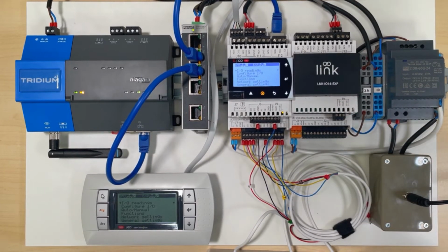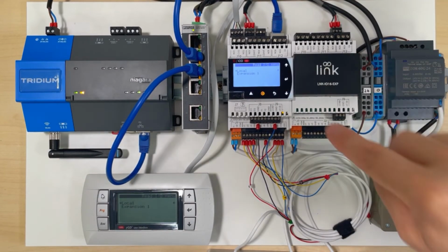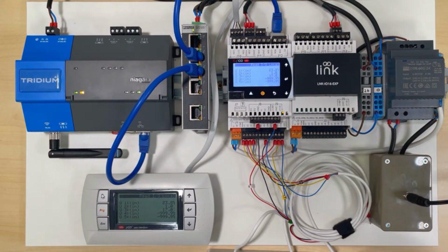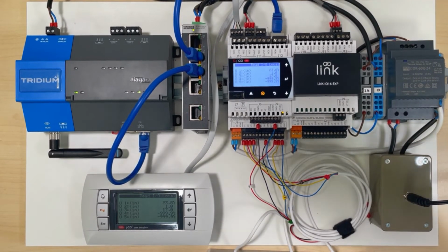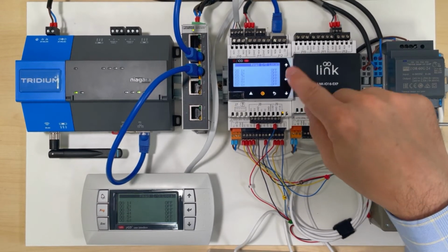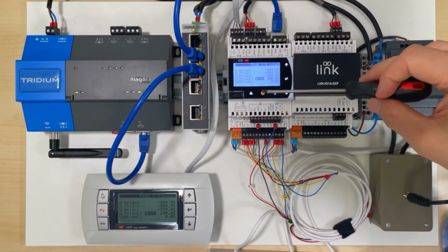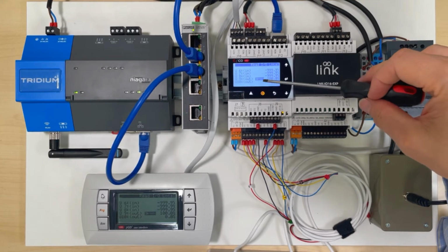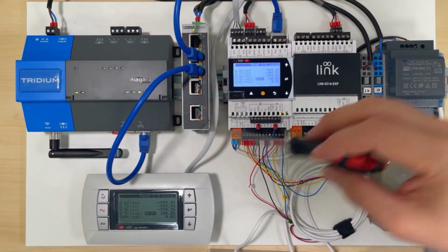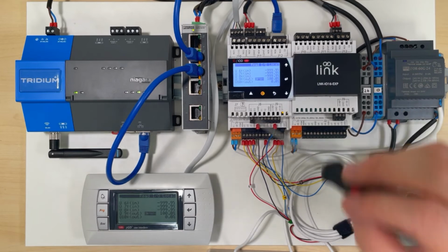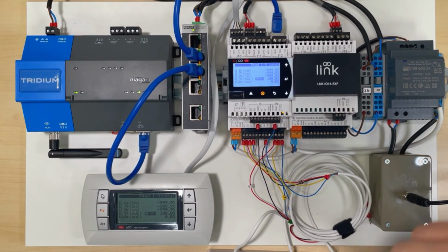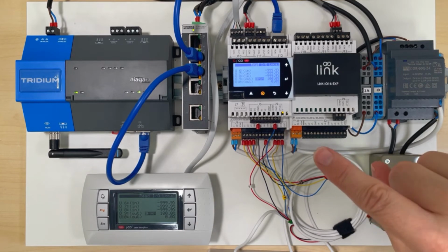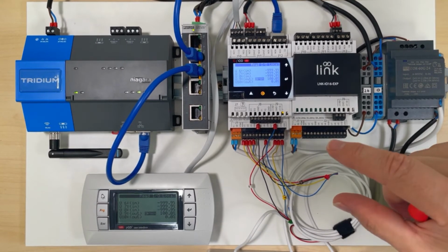So one thing to say about when you're looking at the I/O readings, you saw these little flags here. There's actually a priority of how the outputs, I should say, rather than the inputs, are set. You can see this one says manual at the moment. If there's nothing on it, automatic BMS control is being implemented. But the hierarchy is at the bottom of the priority is the BMS. If the watchdog function kicks in because the BMS isn't communicating, then that will take priority over BMS.